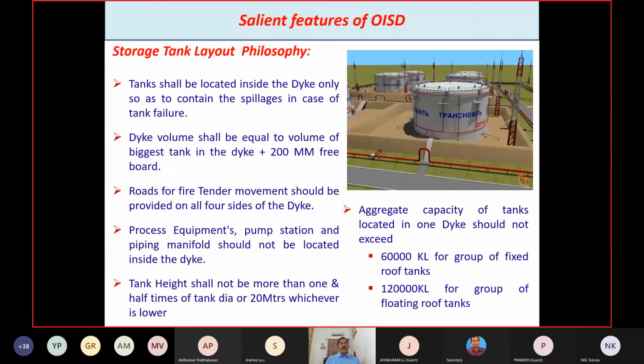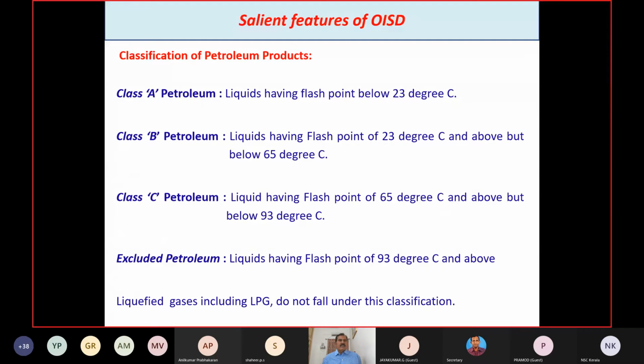And the process equipment, pump station and piping manifold should not be located inside the dike area. Even the earth pit should not be located inside the dike area. It should be outside of the dike area only. And tank height shall not be more than 1.5 times the tank diameter, or 20 meters, whichever is lower. And aggregate capacity of tanks located in one dike should not exceed 60,000 KL for a group of fixed roof tanks and 1,20,000 KL for a group of floating roof tanks. Then we will move on to the next slide.